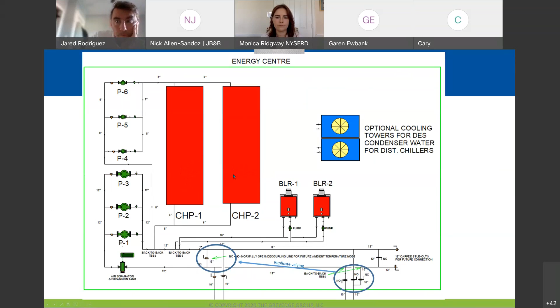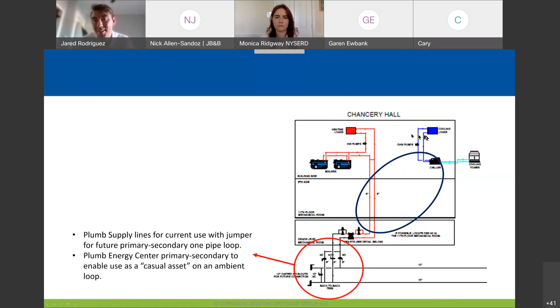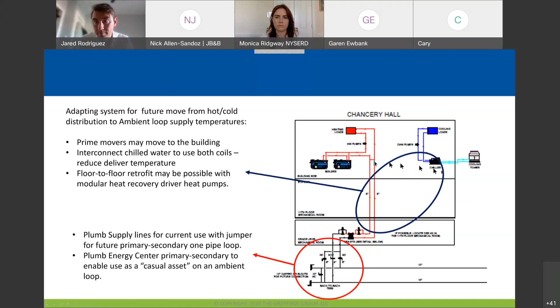We also take a look at this - what we have in our distribution. This is our 2-pipe plumbing, but we need to figure out how to take this from 180 degree distribution down to something much lower. Maybe what we need is a little bit more cooling space. In this case, the building has heating and cooling in large air handlers, so we can start to talk about twinning these coils - and we may change the prime movers while we're at it.